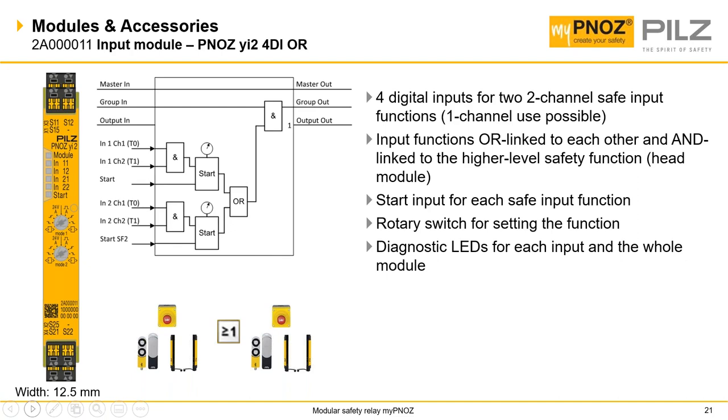Here we are looking at the PNOZ YI2 4DI module. Again, this has four digital inputs for monitoring up to two safe input functions. But with this module, the input functions are OR-linked, as well as being AND linked to the global emergency stop function of the head module. And as you can see, the ever-present LEDs and rotary switches.